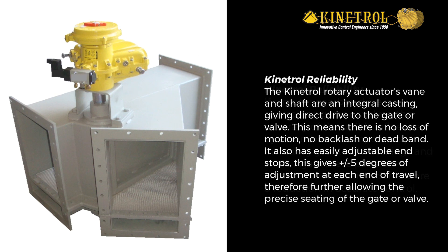The Kinetrol rotary actuator's vane and shaft are an integral casting, giving direct drive to the gate or valve. This means there is no loss of motion, no backlash or dead band. It also has easily adjustable end stops, giving plus or minus 5 degrees of adjustment at each end of travel, therefore further allowing the precise seating of the gate or valve.